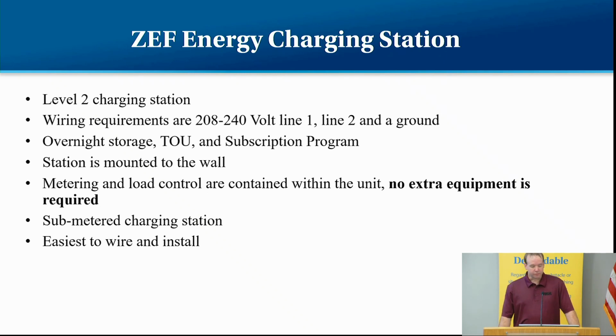The ZEF Energy Station is a level 2 charging station. Its wiring requirements are 208 to 240 volts, 2 hots and a ground. It's a pretty simple installation. You bring your power to it and you're done. The metering is all built into it. You can use either a Wi-Fi signal, or most of them use cellular. The Wi-Fi is a backup. If the cellular signal is not good enough, they'll switch it over to Wi-Fi so that it'll communicate to the ZEF network that way. As far as the installation in the field, you just have to get your circuit to it and power it up, and then ZEF Energy takes care of the rest.